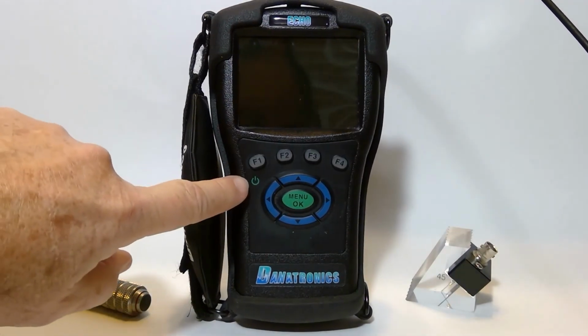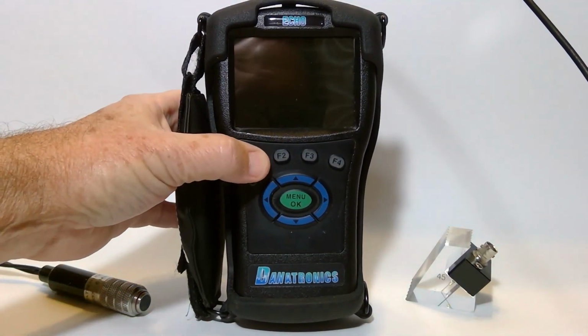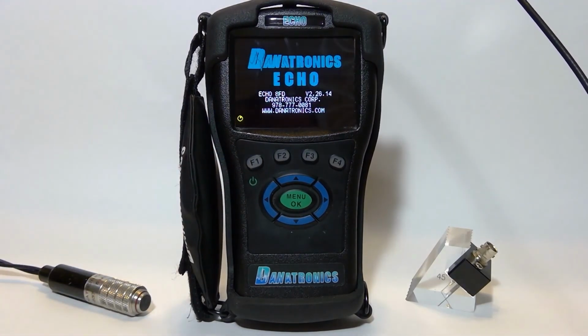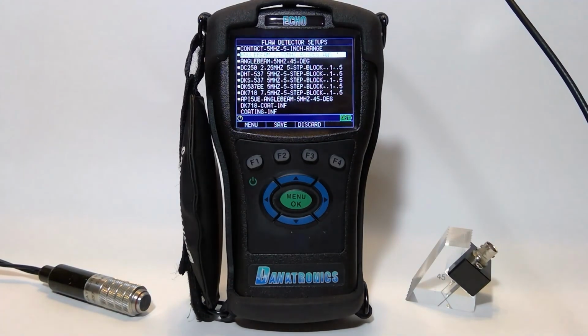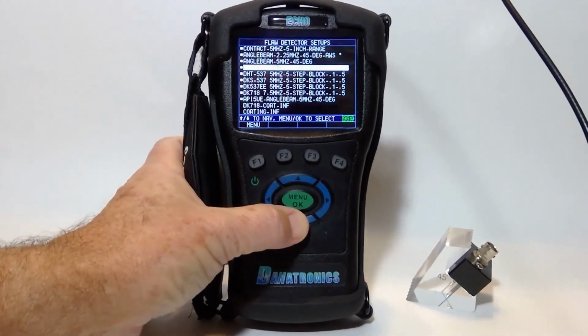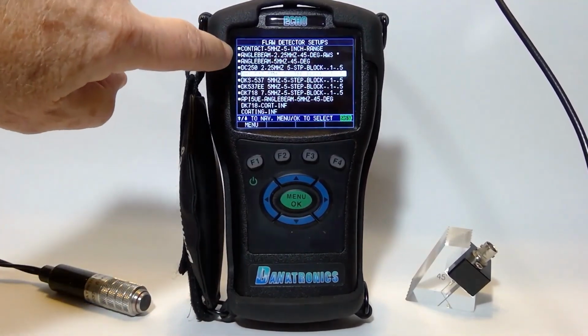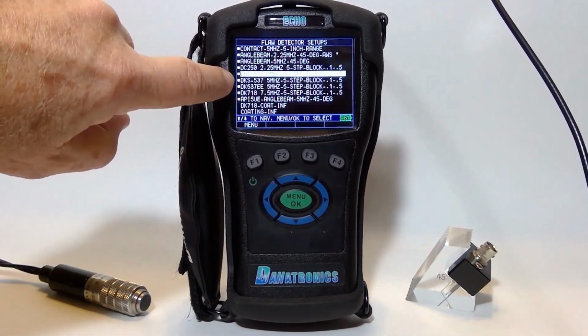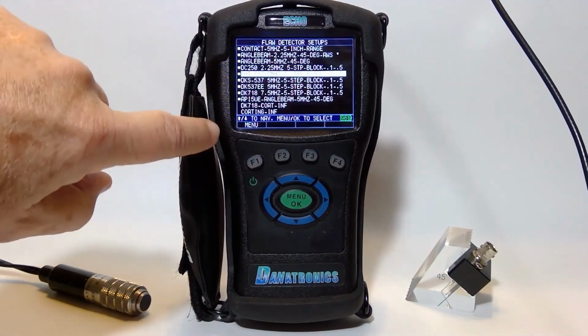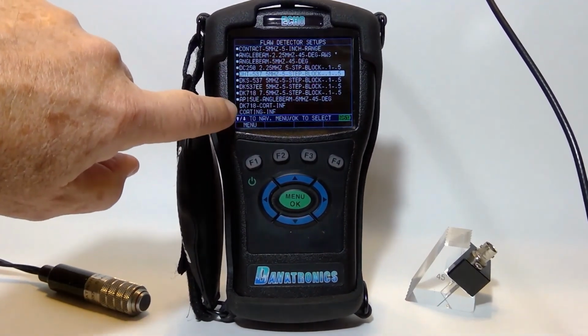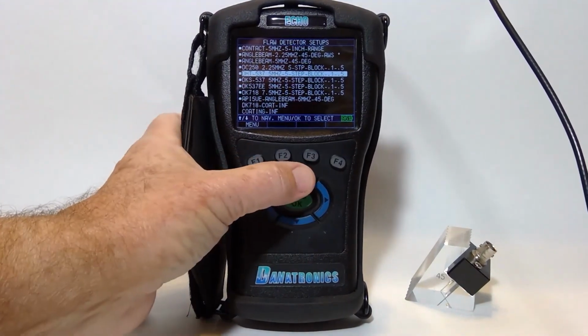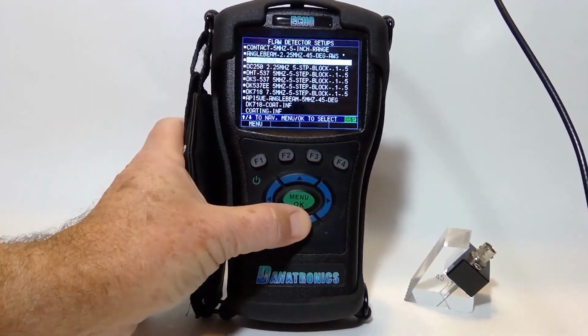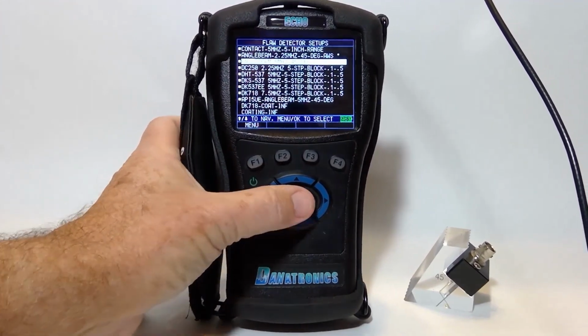So let's turn on the gauge from the F1 power button. In the splash screen, as you can see, the Danatronics information plus the version of software. It'll open up some of the different setups that we already have. The default setups have squares beside them. The user setups that have been stored, as you notice, don't have the squares. So I'm going to highlight my angle beam 5 megahertz 45 degree and hit OK.